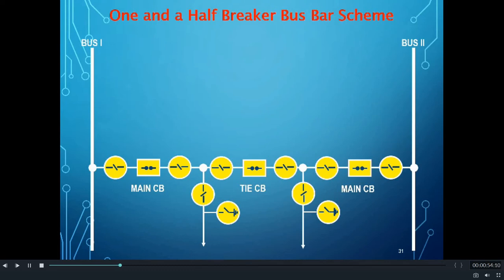Both feeders are connected to both buses through three circuit breakers, so on average for one feeder there are one and a half breakers. This is why this scheme is known as the one and a half breaker scheme. In India, these busbar schemes are used mainly for 400 kV level and above.